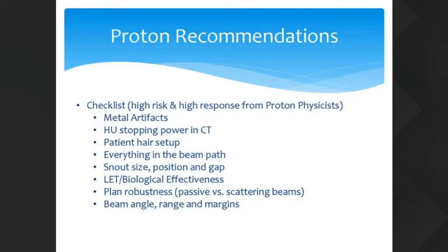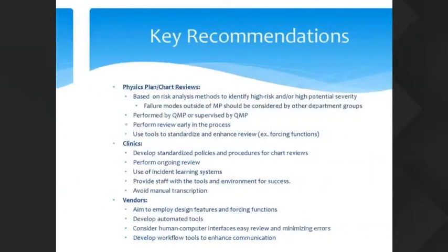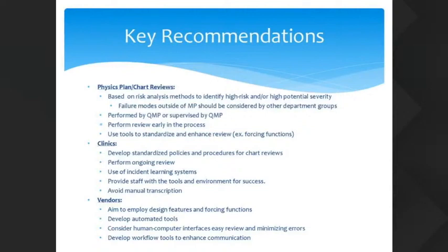And finally, the key recommendations as we walk away from TG 275 and try to implement it into our own clinics, I broke up the key recommendations into 3 categories. The reviews themselves should be based on risk analysis methods, and we used FMEA, and we absolutely encourage clinics to use that.